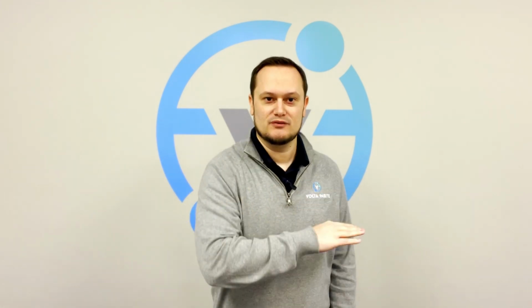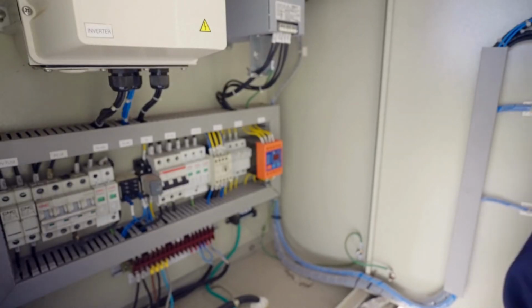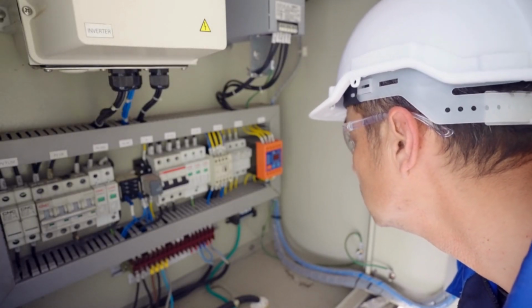The next best place is going to be on the distribution of those pieces of equipment. So if you put it on the distribution of those pieces of equipment, now you're monitoring a lot more. So you can tell if it's from any of the downstream pieces of equipment or if it's coming from outside. And then the final best location, of course, is going to be at your mains, at the utility mains, to be able to really just immediately provide and prove if it's coming from the utility or coming from within your plant.